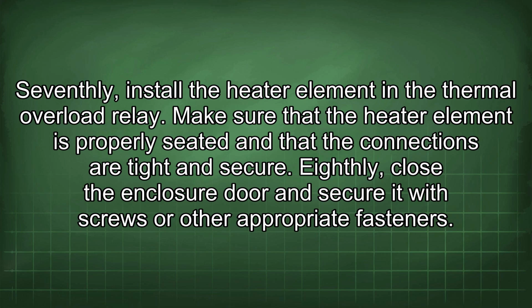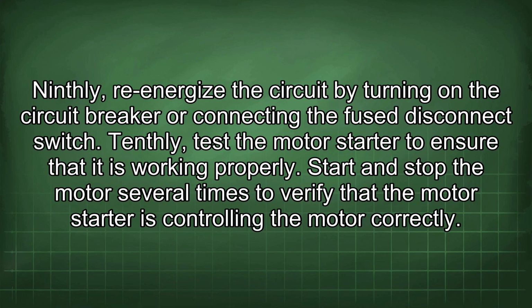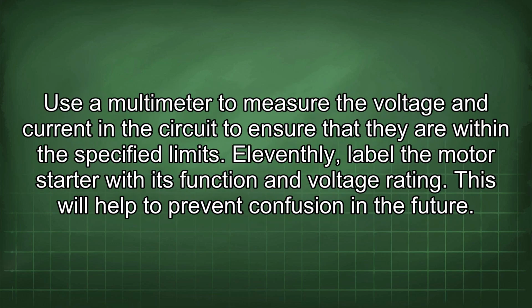Eighthly, close the enclosure door and secure it with screws or other appropriate fasteners. Ninthly, re-energize the circuit by turning on the circuit breaker or connecting the fuse disconnect switch. Tenthly, test the motor starter to ensure that it is working properly. Start and stop the motor several times to verify that the motor starter is controlling the motor correctly. Use a multimeter to measure the voltage and current in the circuit to ensure that they are within the specified limits. Eleventhly, label the motor starter with its function and voltage rating. This will help to prevent confusion in the future.